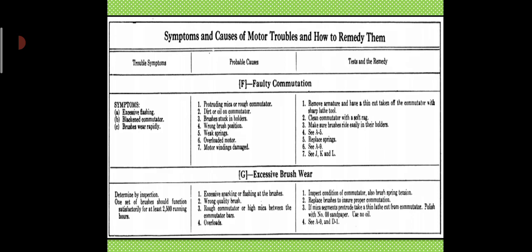Now, checking of the electric motors. When a motor fails, it is often difficult to see why it failed just by looking at it. A motor placed in storage may or may not be working regardless of its physical appearance. A quick checkout can be done with a simple ohmmeter, but there is a lot more information to collect before actually putting it to use. At no time during the motor checkout is power required. If it is connected, disconnect it before attempting the steps below. First, check the outside of the motor, check the nameplate on the motor, check the bearings, check the windings, and troubleshoot other potential problems like checking the start or run capacitor used for starting or running some motors. Check the rotor and bell housings of the motor. Check the fan. Choose the right motor for the conditions in which it will be run.